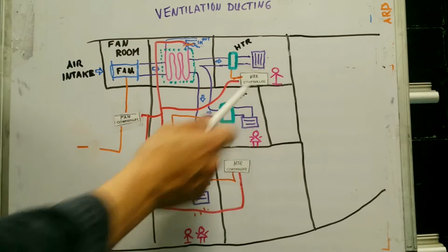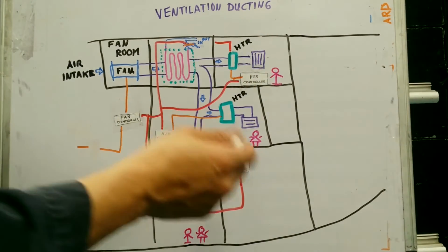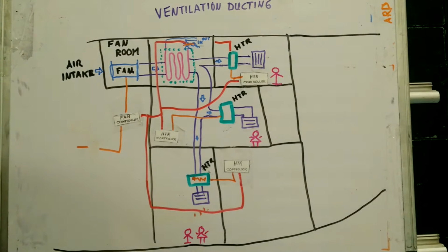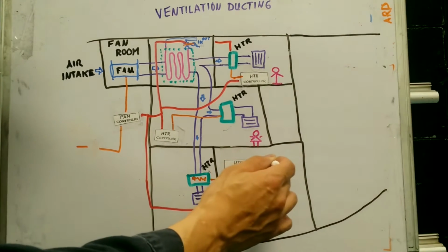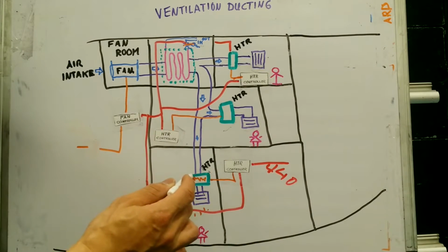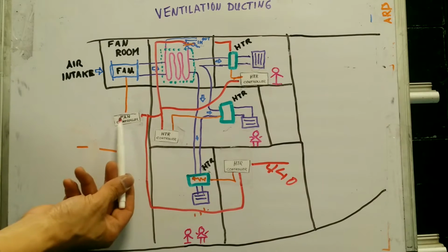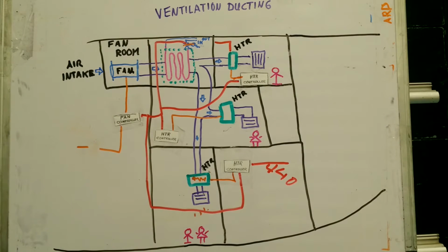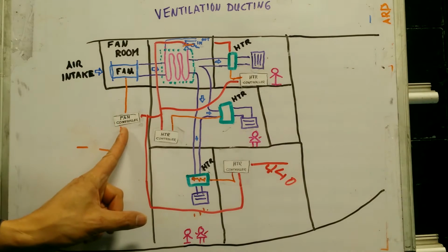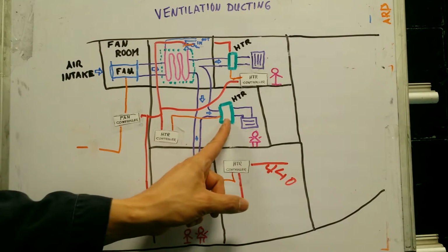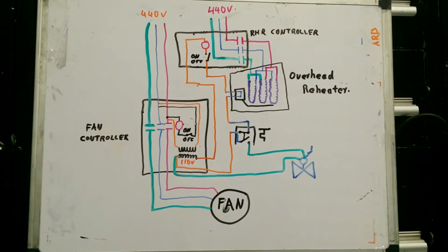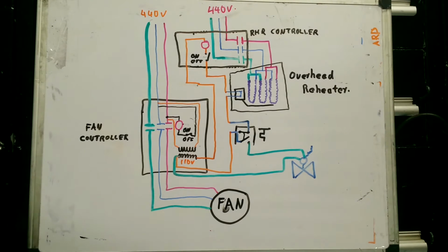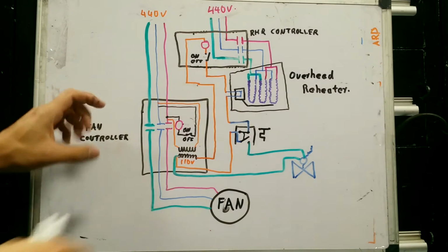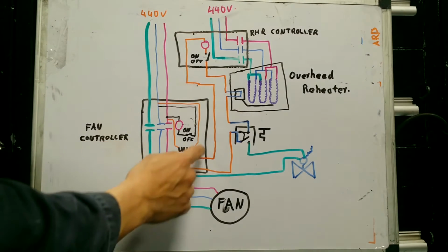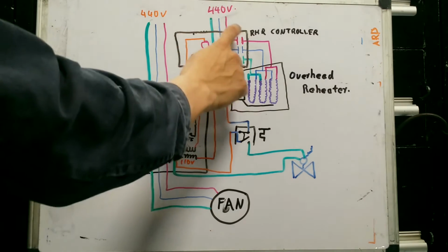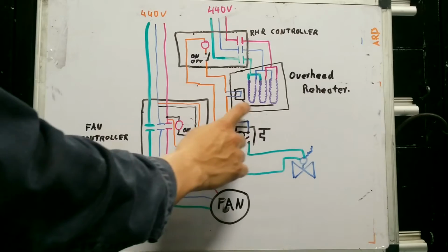However, each local heater does have its own 440 going into it, because heaters themselves consume a lot of power. So even though 440 is applied to them, the 440 is for the actual heater, but the control side power comes from the fan controller. Now let me talk about just one particular fan controller and one heater controller along with its associated heater. I hope not to be too confusing over here, but this box represents a motor controller, this one represents a heater controller, and this one represents the overhead heater.